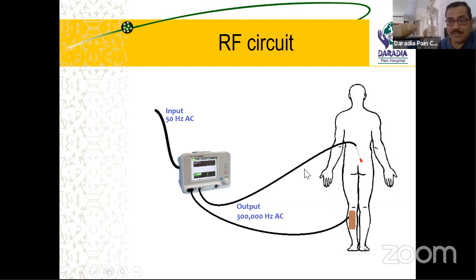So remember, if the length of this needle, the bare or uncovered area, is more than 15 millimeter, 1.5 centimeter, then there will be no lesion. This radiofrequency needle is basically like a nerve stimulator needle. It is insulated except the tip. The tip is exposed, and that is the active electrode. Inside it, we put the thermocouple. This exposed tip should not be more than 1.5 centimeter. If it is more than 1.5 centimeter, what will happen? The electricity will be dispersed, and there will be no good lesion there. So this is how the electricity is transmitted to the body's electrolytes, and the circuit is completed. And this is the circuit for the conventional thermal radiofrequency.